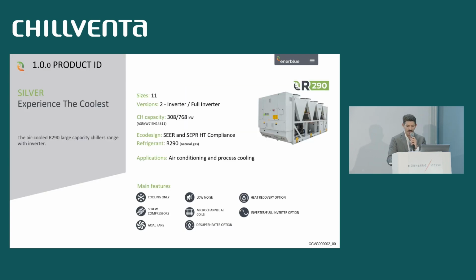So as mentioned, the new range is called Silver. It's an air-cooled unit filled with refrigerant propane, and the cooling capacity goes between 300 and 770 kW at nominal conditions, so air temperature 35, outlet water temperature 7 degrees according to the norm. The range was developed with 11 sizes, without inverter, with double inverter, so full inverter. The unit is equipped with semi-hermetic screw compressors.